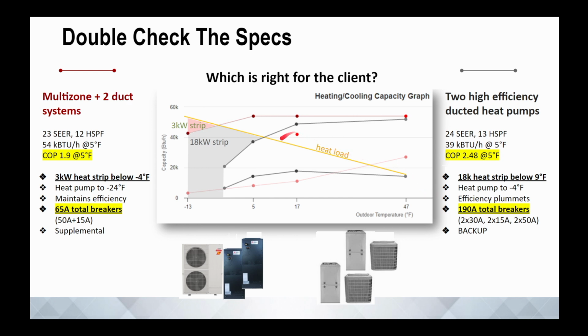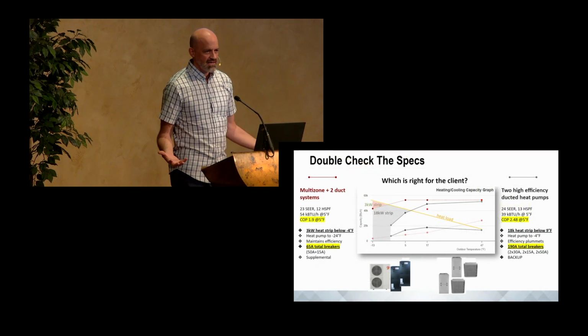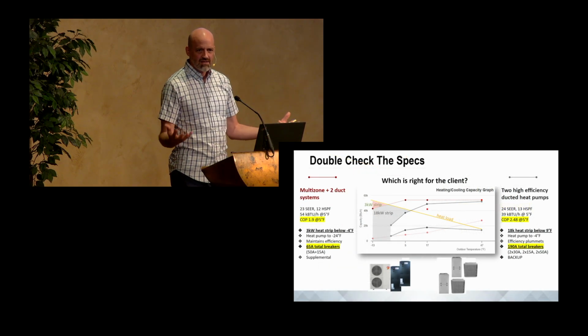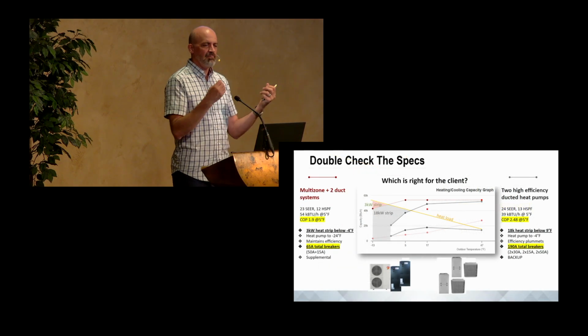Yes, but as the temperature drops, the capacity drops. Right? And at -4, the system is off. So you have to put in an 18 kW heat strip or something similar to heat the house to make up the difference for when that system diminishes or is off. And that's an entirely second system, right? It's a backup system, which is fine. It's not a bad strategy.